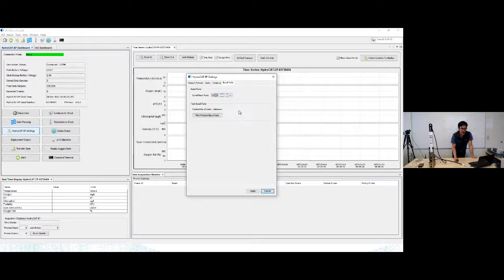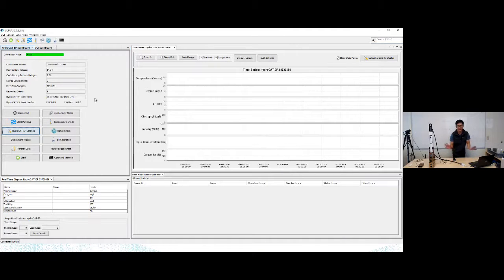And then finally, we have the baud rate. Default is 19200. I recommend just leaving it at this unless you're deploying your HydroCAT EP on a system with maybe a really long RS-232 cable where you need to turn down the baud rate in order to get your data. 19200 is pretty reliable. So, okay, I didn't really change any settings here besides the output format. I'm going to click apply, and my settings are now programmed into my HydroCAT EP. So that's HydroCAT EP settings from within UCI.